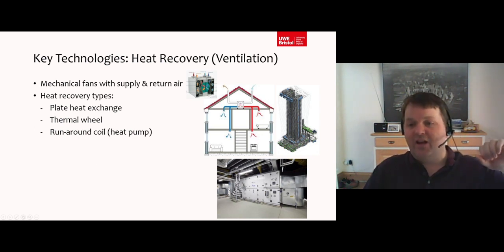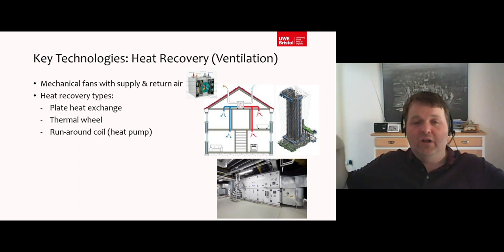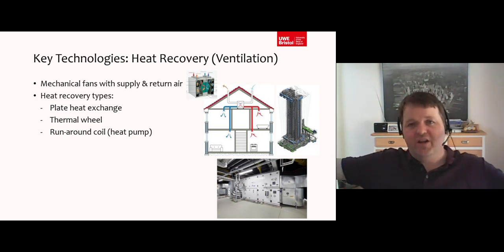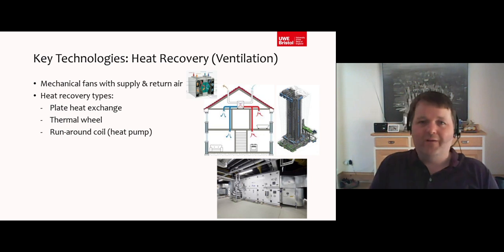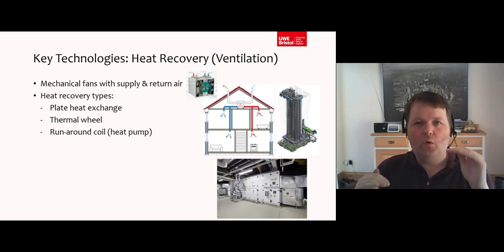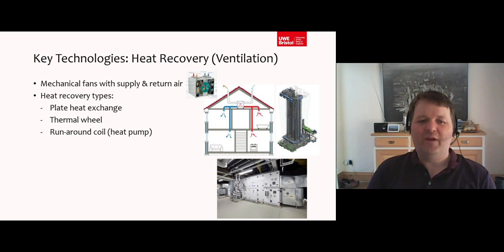If you just cannot coordinate your return air to come too close to the exhaust air to use one of those two, you could effectively use a heat pump, or called a runaround coil. You stick one end in the exhaust air, and you stick the other end in the fresh air, and you do an air source heat pump, a runaround coil in that space, and it tends to be slightly less efficient than the other two. But the good thing about a runaround coil with a heat pump is you're not limited in temperature. You can actually keep pumping heat out of a colder space into a hotter space using the vapor compression cycle, which I explained in the video on heat pumps.